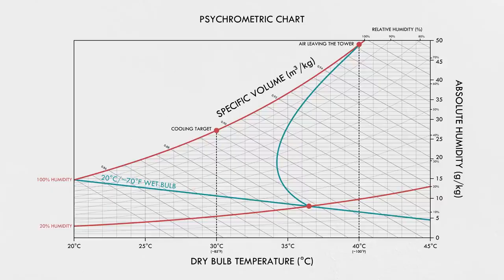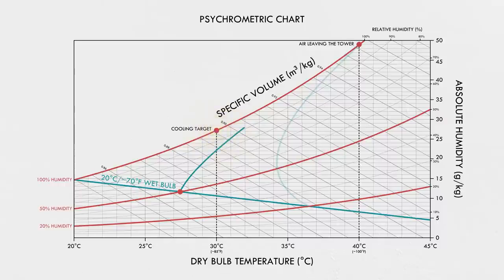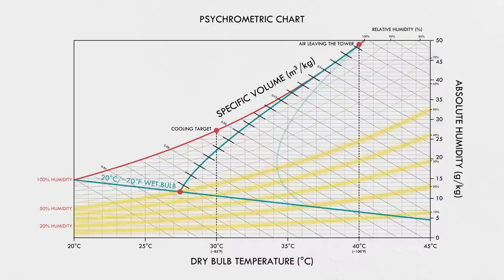But watch what happens if you increase the relative humidity of the ambient air to 50%. The line still curves initially toward the outlet temperature before heading to the inlet temperature as it moves through the fill, but it decreases in density consistently along its entire path through the fill. So cooling engineers say that for a given wet bulb temperature, you get a better draft as relative humidity goes up. It seems counterintuitive, but another way to look at it makes more sense.